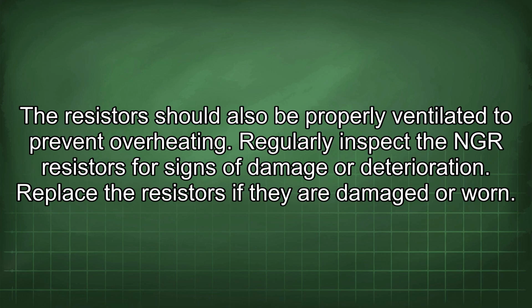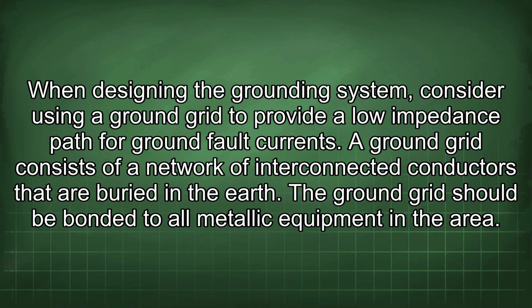Regularly inspect the NGR resistors for signs of damage or deterioration. Replace the resistors if they are damaged or worn. When designing the grounding system, consider using a ground grid to provide a low impedance path for ground fault currents.